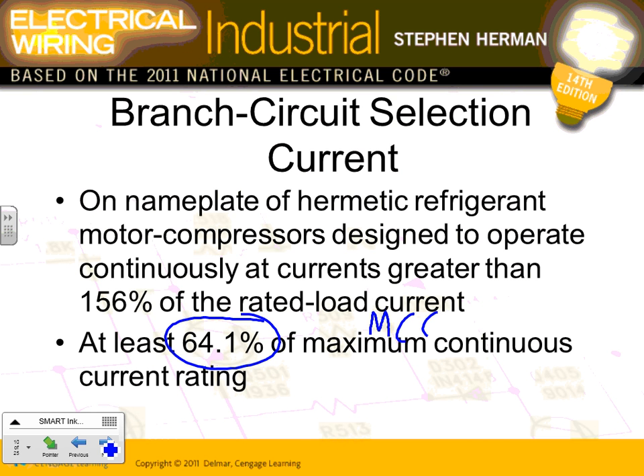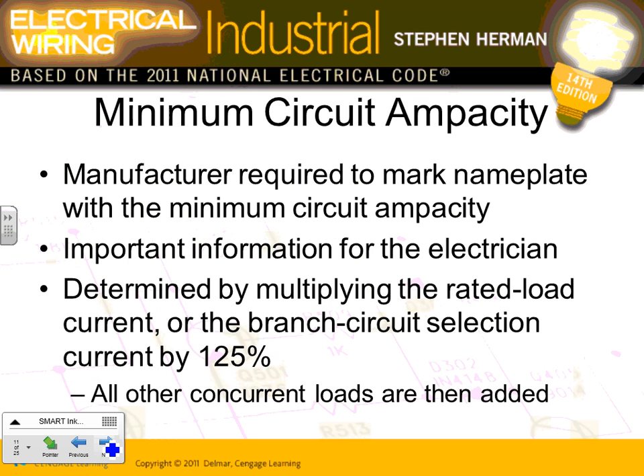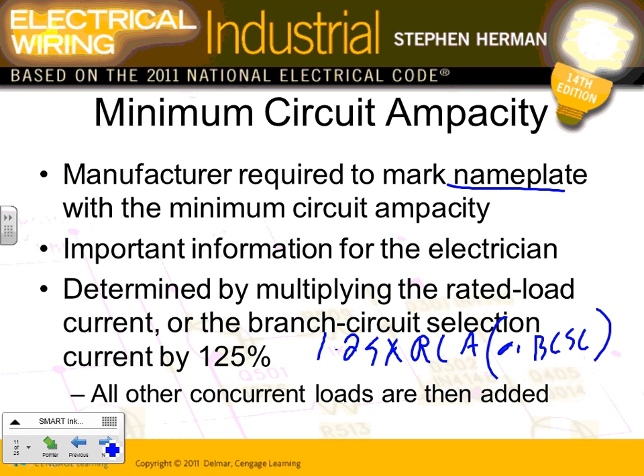What do we care about, guys? We care about minimum circuit ampacity and maximum overcurrent device. If they're not given, they have to give you branch circuit selection current or rated load amps, and from either one of them you can size, like we did in the example before. Minimum circuit ampacity is done completely for you on the nameplate. The way they size it, like I said, you take 1.25 times rated load amps or branch circuit selection current, whichever is larger, and that sizes the conductor for you. No need to do it, it's already sized for you.